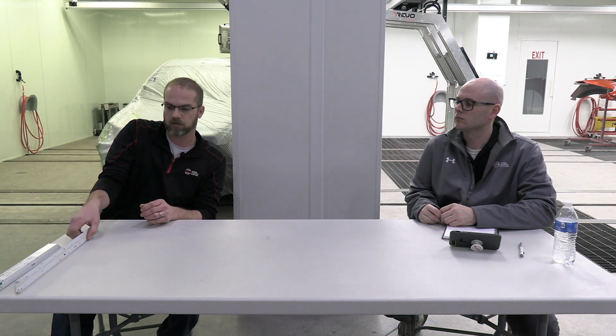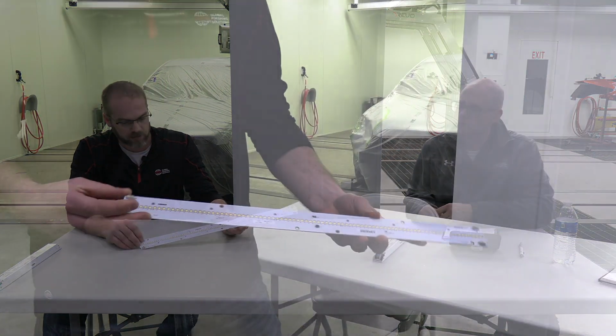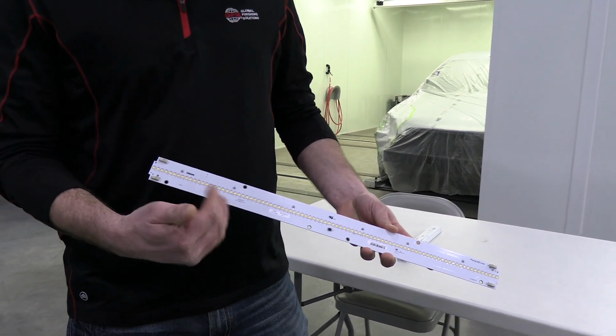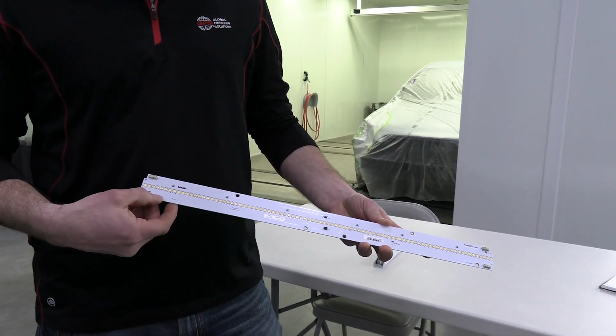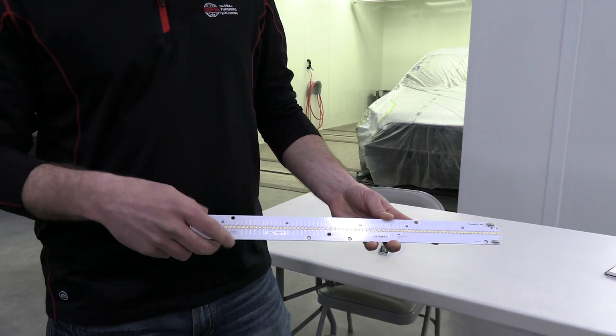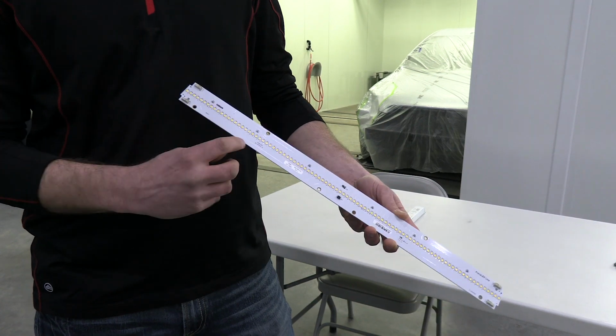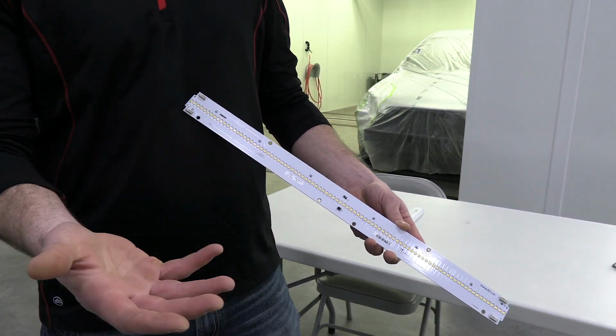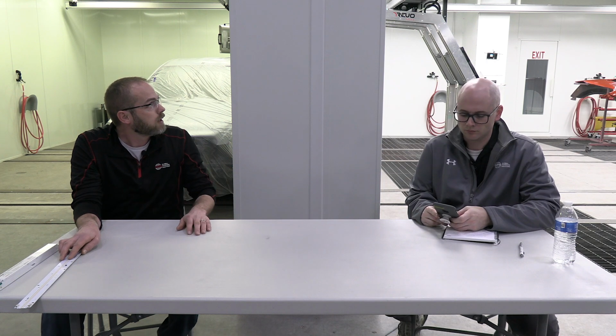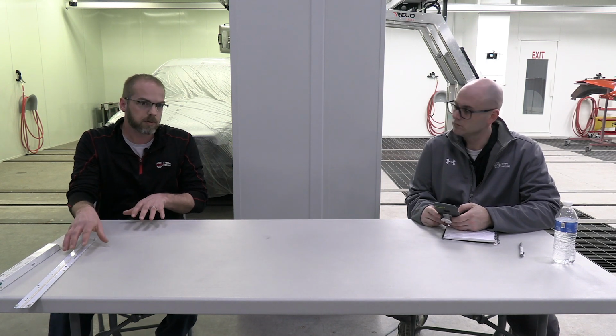We're using GFS lights in this booth. The way we've designed our lights is we run them on a standard T8 fluorescent fixture, which uses a high voltage ballast. The tubes themselves will have a board something like this inside. It'll have individual LED diodes, light emitting diodes on it. The voltage from the ballast is a high voltage. The board will convert it to a lower voltage that the LEDs use, and we'll have the light coming out of the tube as you see here. So that's the main difference in the technology behind it.